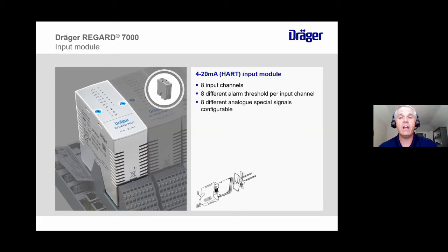We have 8 different analog special signals that are configurable. So what is an analog special signal? This is the diagnostic stuff that's available. Basically, if you have some sort of sensor fault or IR beam block or some fault going on with the transmitter or the sensor attached to that transmitter, the milliamps will drop below 4. So maybe beam block means 3 milliamps, or a sensor not connected is 1.5 milliamps. But you have up to 8 special signals that you configure per module.